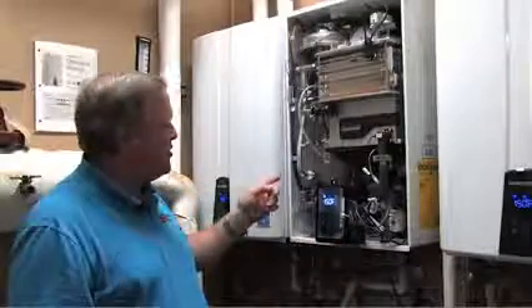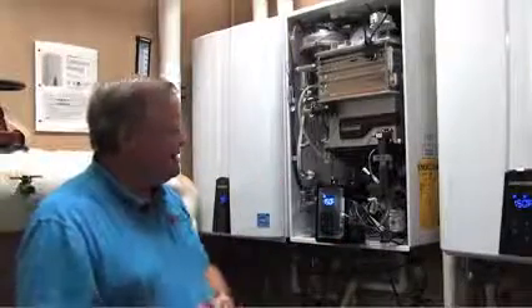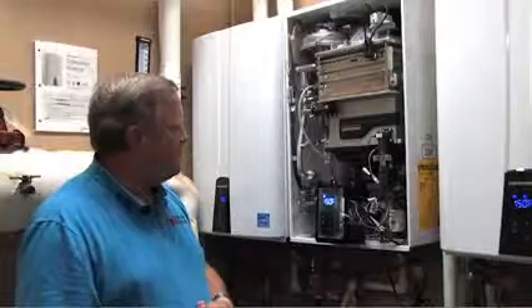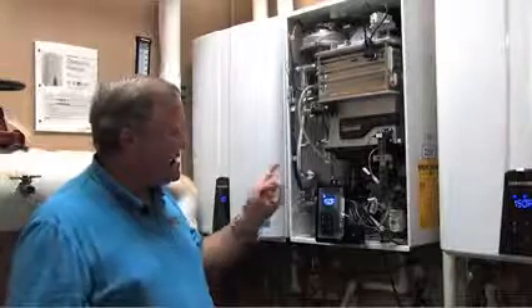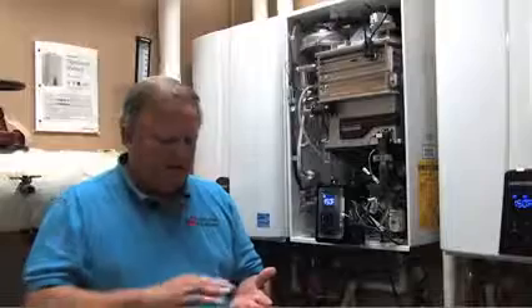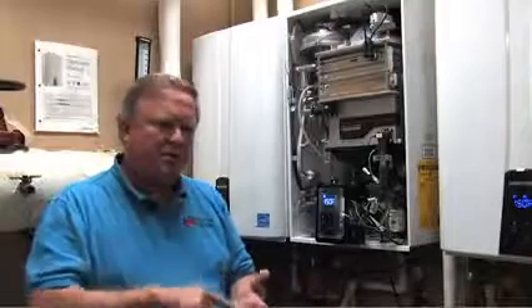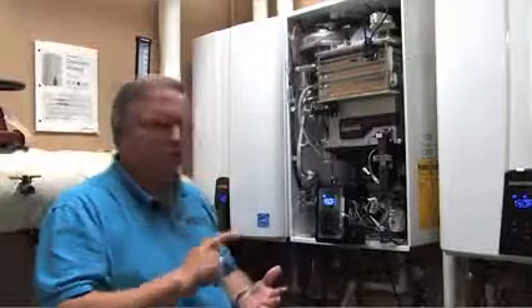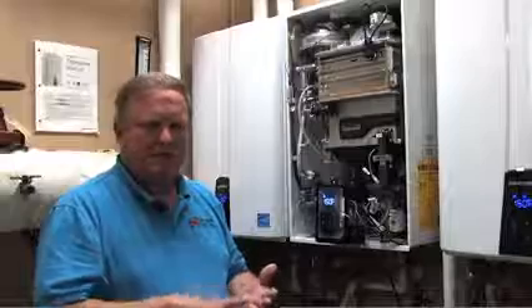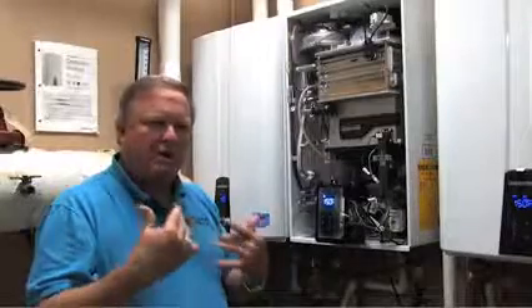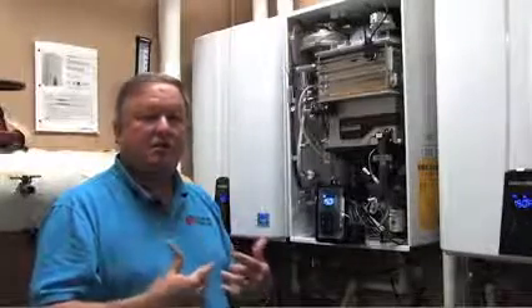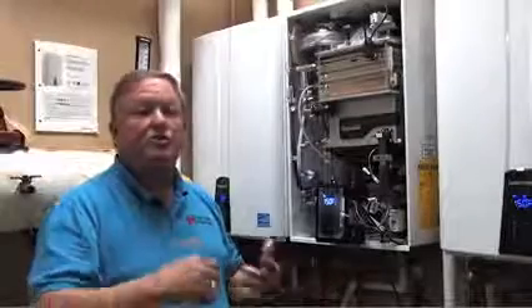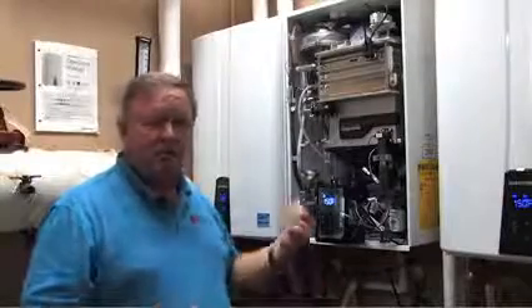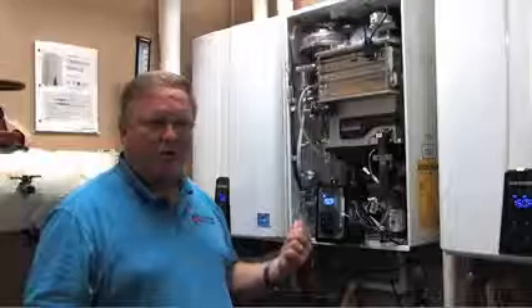Another feature that is unique to the Navien is the buffer tank. And a buffer tank does a couple things for us. One, we have the lowest flow rate to fire the unit. And what that means is at less than 0.1 gallon a minute, say a trickle of hot water in a bar sink or a small sink, this unit will go to minimum fire and produce hot water.